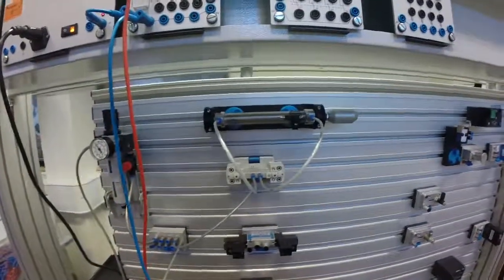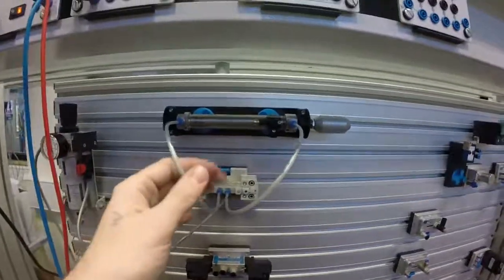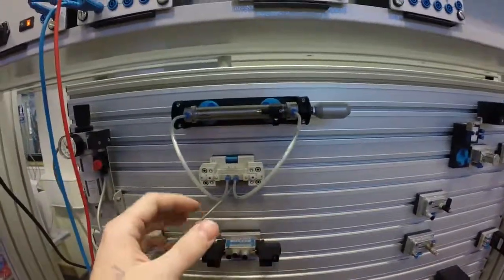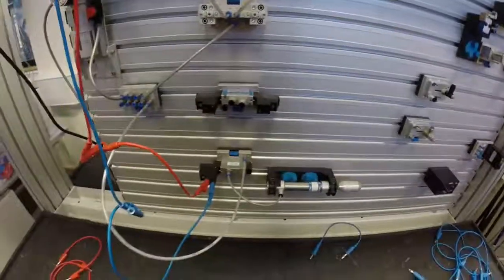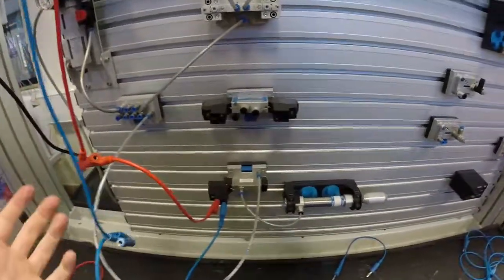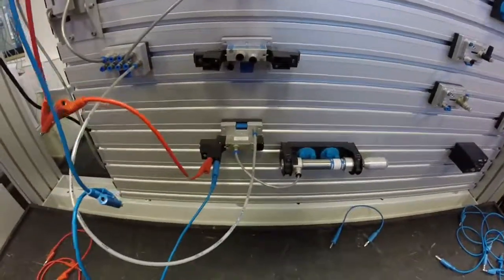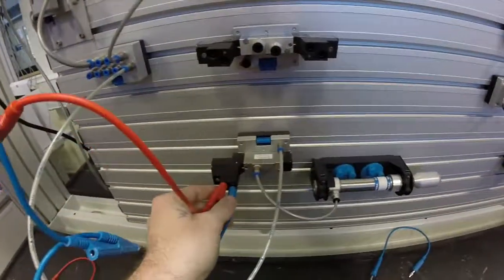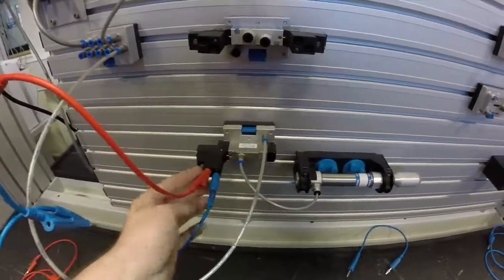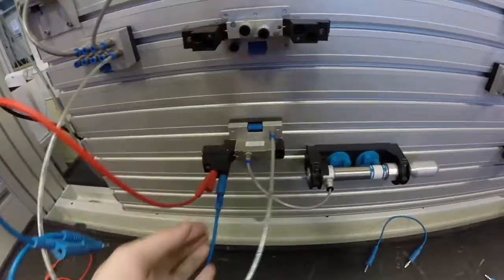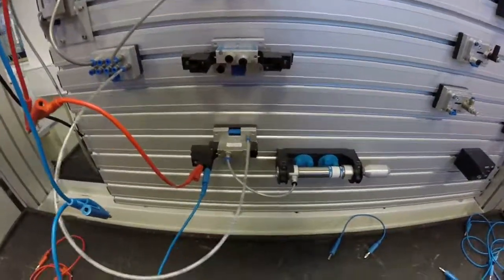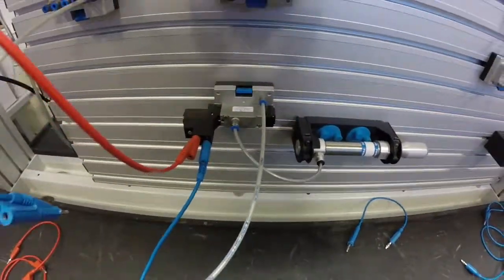So because we're dealing with electrical power and pneumatics, if the circuit isn't working, there could be a problem either with the pneumatics or with the electro stuff. So the LED at least lets us know if that turns on. Well, then we've got power, the solenoid is operating, and there may be a problem with our piping with the pneumatics. So it's good for fault finding as well, those little lights.